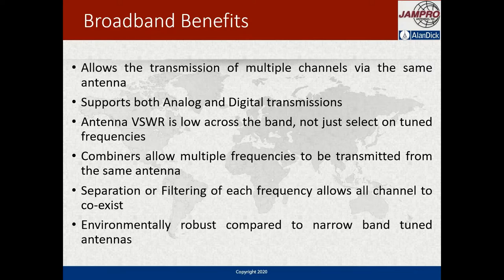What the combiner does is get the output from each individual transmitter and allow them to add together to one output, which can then be fed into the transmission line and up to the antenna. There are various types of combiners depending on power — if power is higher, the combiners need to be larger to handle it. Also, depending on frequency: if the frequencies are very close together, you need a combiner that provides isolation between the transmitted channels, which requires the combiner to work harder.